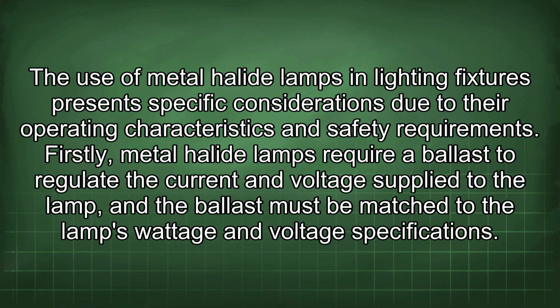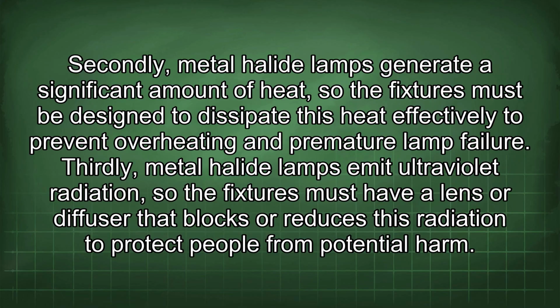The use of metal halide lamps in lighting fixtures presents specific considerations due to their operating characteristics and safety requirements. Firstly, metal halide lamps require a ballast to regulate the current and voltage supplied to the lamp, and the ballast must be matched to the lamp's wattage and voltage specifications. Secondly, metal halide lamps generate a significant amount of heat, so the fixtures must be designed to dissipate this heat effectively to prevent overheating and premature lamp failure.